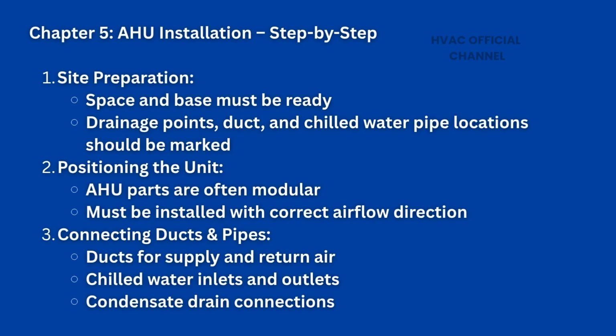Chapter 5. AHU installation, step by step. Site preparation. Space and base must be ready. Drainage points, duct, and chilled water pipe locations should be marked. Positioning the unit. AHU parts are often modular. Must be installed with correct airflow direction.